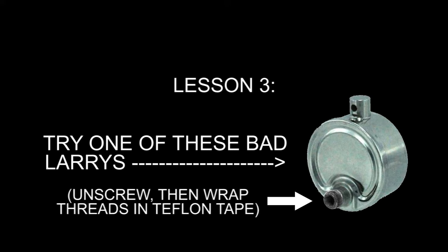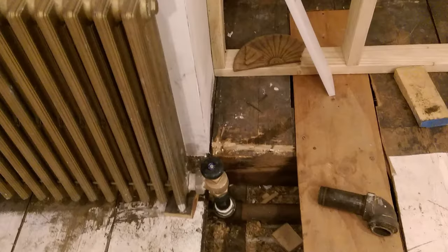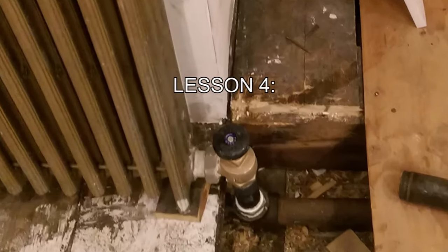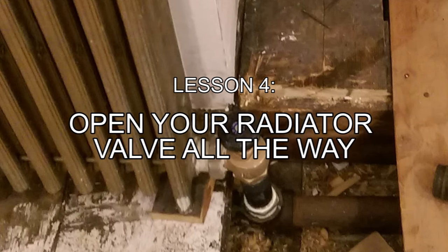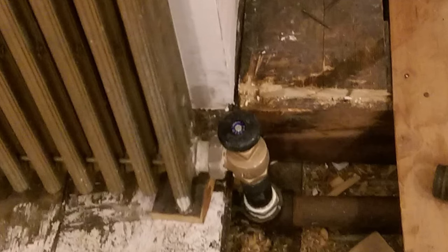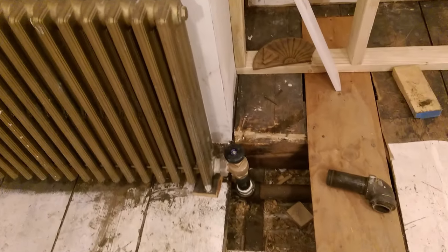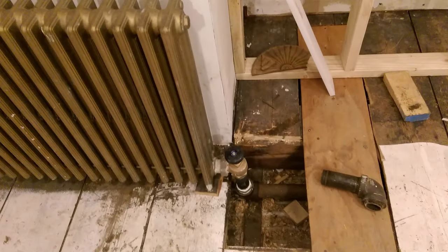And man, that was a lot of technical details, so let's take a brief intermission here with easy lesson number 4. Make sure that your radiator valve is open all the way by turning it counterclockwise. If it's defective and rusted shut though, you might have to replace it. If you do, you will need a pipe wrench, pipe dope on the threads, and an appropriately sized radiator valve. Do this job only when the boiler is shut off, and preferably not in the dead of winter.